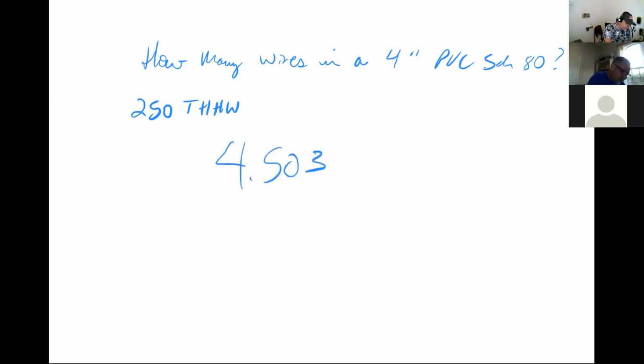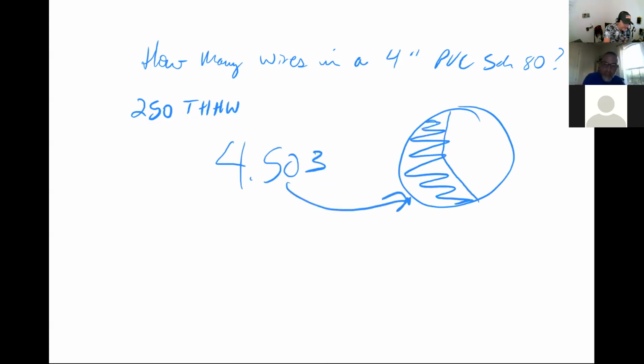4.503. If I look at a 4-inch conduit and say, okay, 40% of that is going to be this space right here, that number represents that space. It's the allowable fill area, right? Be careful, because that 40% they're talking about in the code book is if they take all of these wires and squeeze them so tight there's no air gap.